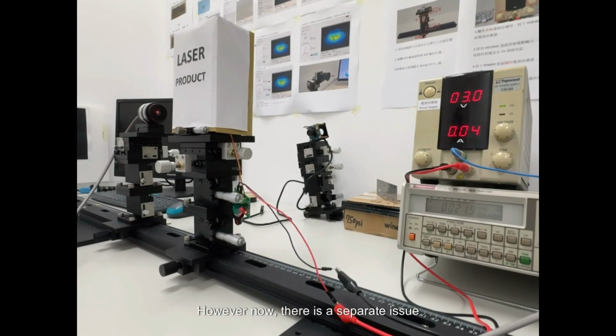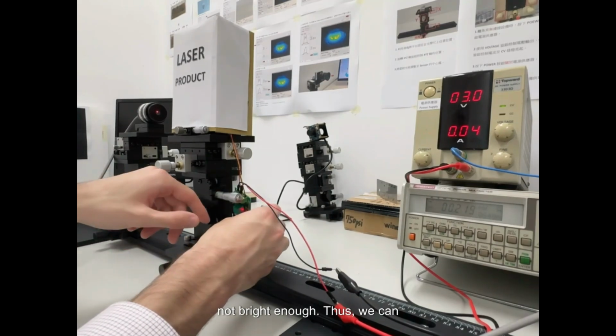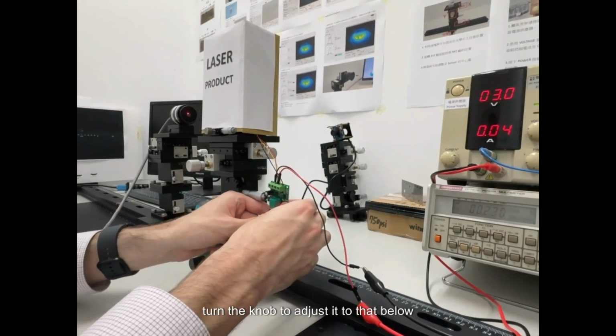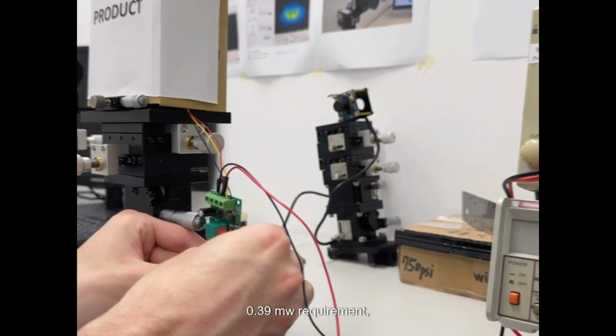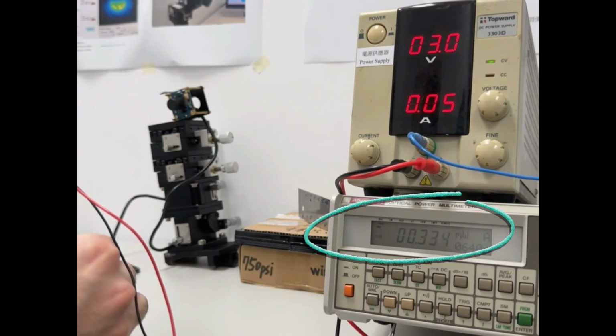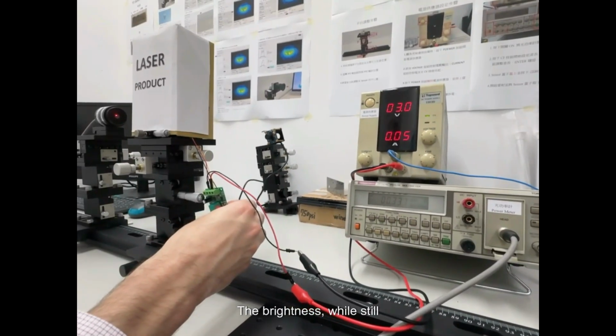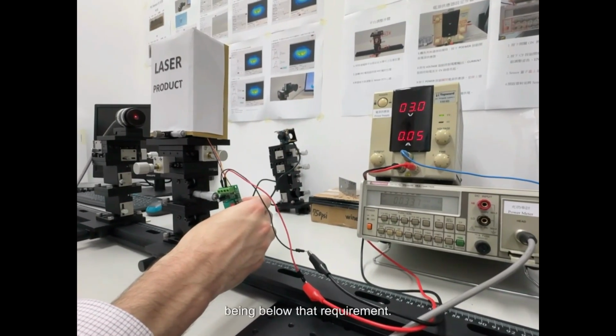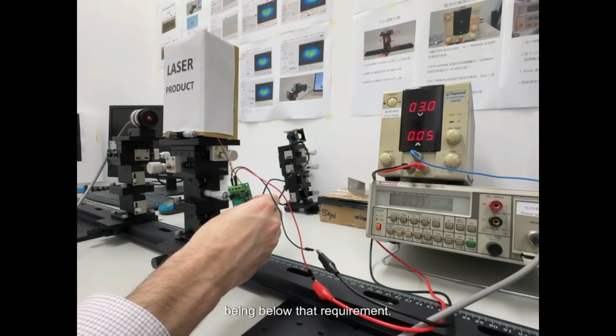However, now there is a separate issue where the laser beam may not be as bright as customers may need it to be. While they still want it to comply with class 1 laser product, the laser beam is not bright enough. Thus, we can turn the knob to adjust it to that below 0.39 milliwatt requirement. So we'll increase the brightness while still being below that requirement.